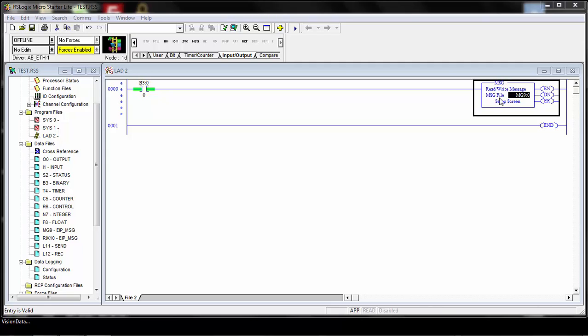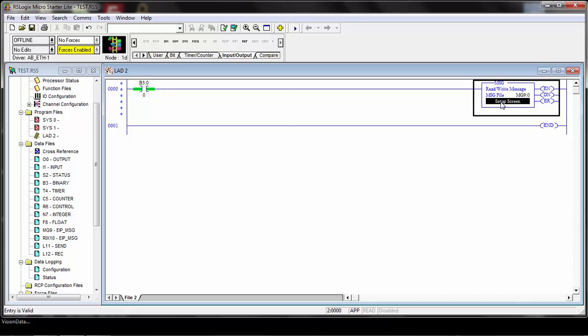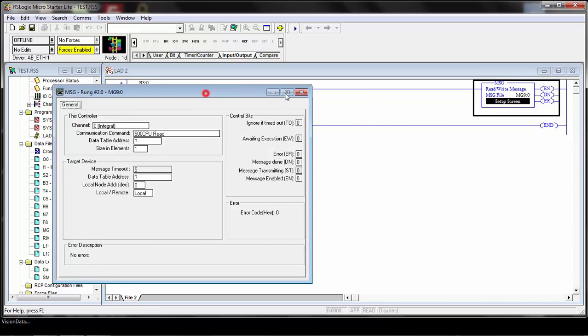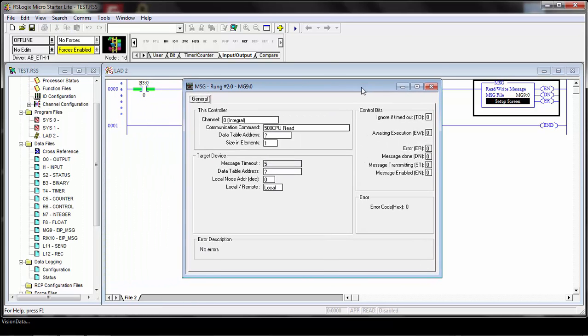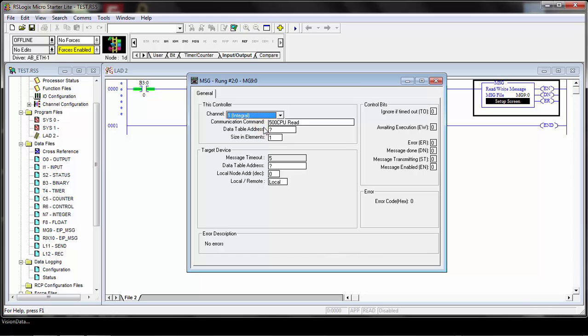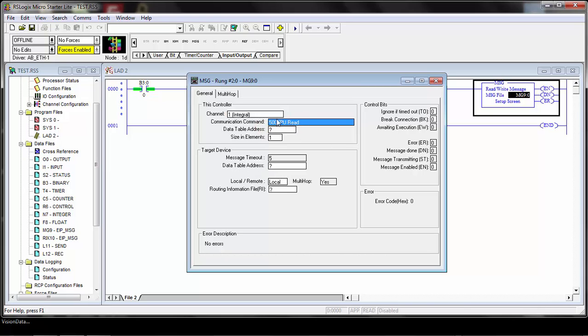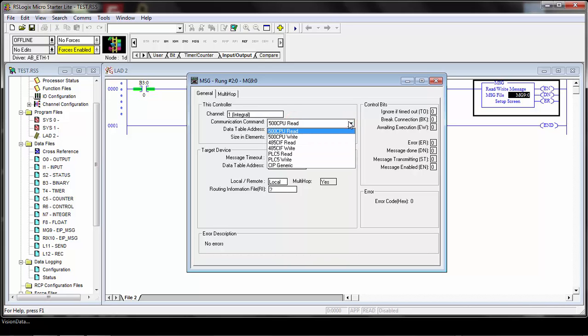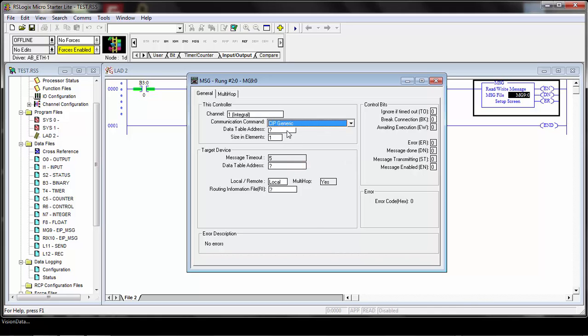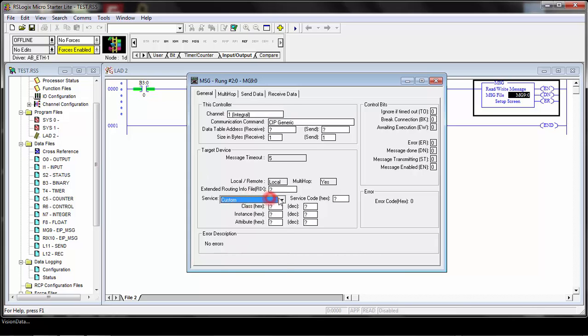Once you've referenced your message data type for the message file, you can set up the rest of the message. Just double click the setup screen here, and that will bring up the message setup. For the channel, you need to make sure you choose the Ethernet channel, because this is an Ethernet type of function. Once you choose that, it'll set up the rest of the message. For the communication command, we're going to choose CIP generic, and that's for the explicit message setup. Once you choose that, it'll open up these other fields.